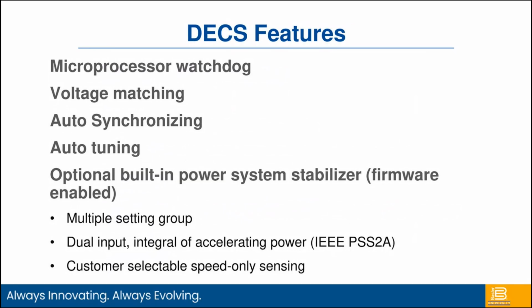We also can do microprocessor watchdogs, voltage matching and auto synchronizing internally to the DECS, so we don't need a separate box for those things. Auto tuning, which we talked about. And in some cases, customers may need a power system stabilizer. So this will allow us to add a multiple setting group power system stabilizer. We can use different models depending on what the application is. So it is an option within our digital products.